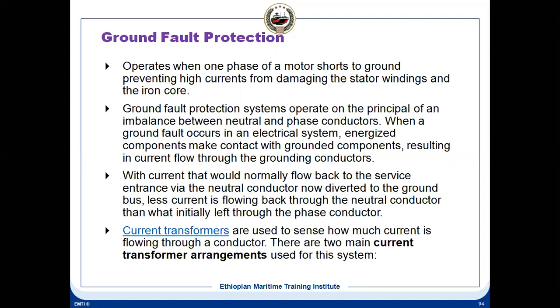Whenever a ground fault occurs in an electrical system, energized components make contact with grounded components, resulting in a current flowing through the grounding conductors. So current that would normally flow back to the service entrance by the neutral conductors is now diverted to the ground. Less current is flowing back through the neutral conductors than what initially left through the phase conductor.